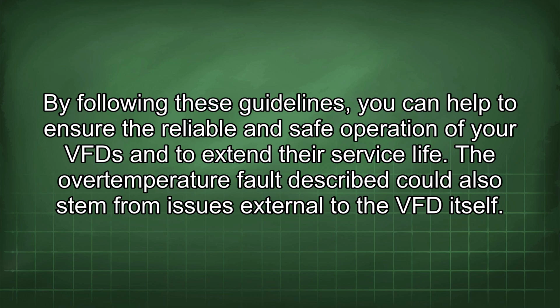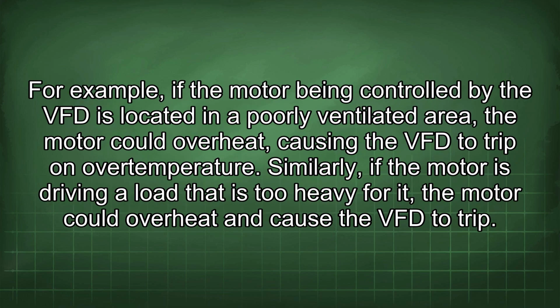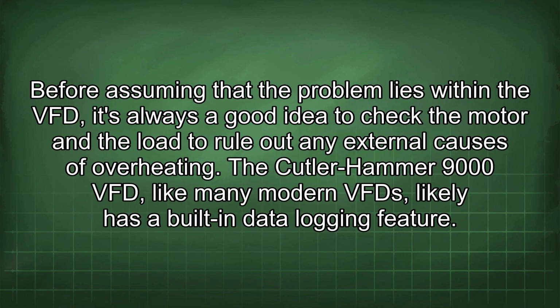The overtemperature fault described could also stem from issues external to the VFD itself. For example, if the motor being controlled by the VFD is located in a poorly ventilated area, the motor could overheat, causing the VFD to trip on overtemperature. Similarly, if the motor is driving a load that is too heavy for it, the motor could overheat and cause the VFD to trip. Before assuming that the problem lies within the VFD, it's always a good idea to check the motor and the load to rule out any external causes of overheating.